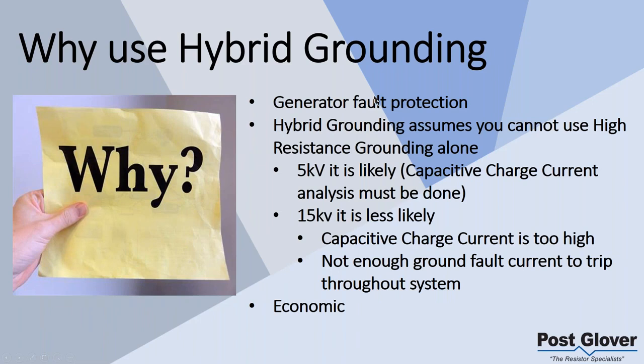So, like I mentioned before, for generators, hybrid grounding assumes you cannot use high resistance grounding. For most of the research I've done and most of the applications I've seen, it's usually at the 15 kV level. One of the reasons, I believe, is that nowadays at 5 kV it's more likely that you could use high resistance ground by itself. If you have a combination of high resistance ground and low resistance ground, you're basically adopting the benefits of high resistance ground, which are lack of damage to your equipment over an extended, continuous period of time. If you can just use high resistance by itself, then why would you use hybrid essentially?